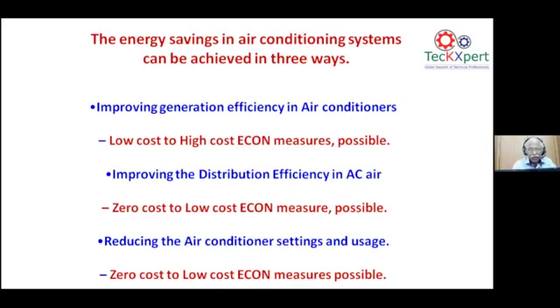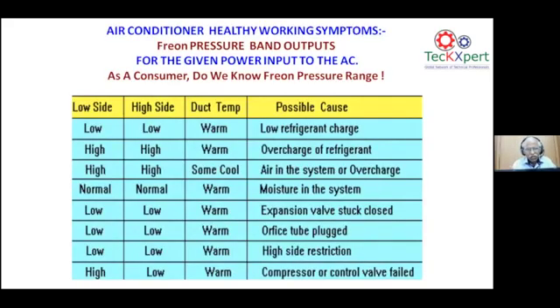Definitely three areas are to be attacked: the usage side, the distribution side, and the generation side. On the generation side, especially on the Freon circuits, we need to look at where and how we are maintaining. If you have a Freon refrigerant charge, over a period of time, over a year, it has leaked out, it has become low on the low side and high side, and the duct temperature is warm. That is the cause.